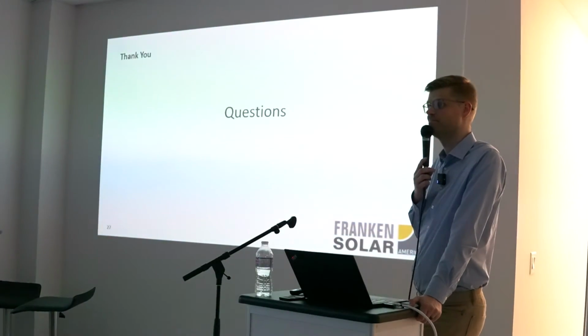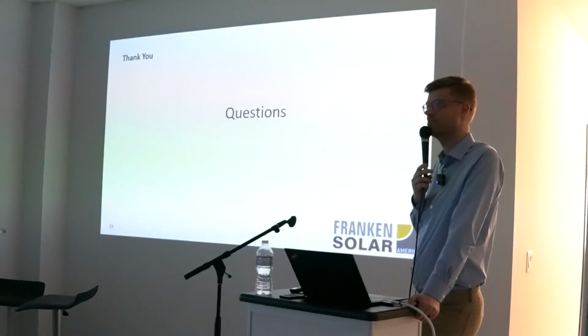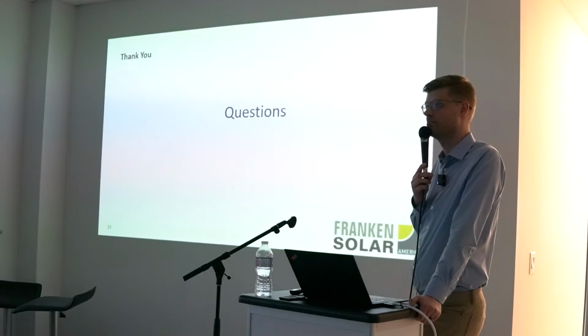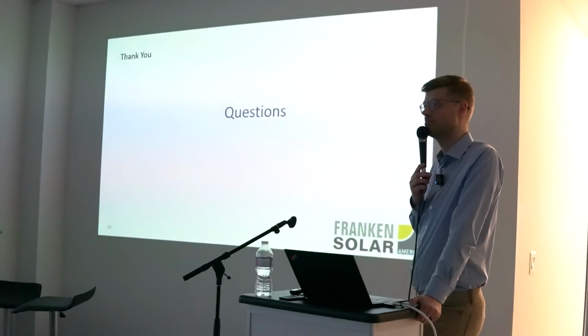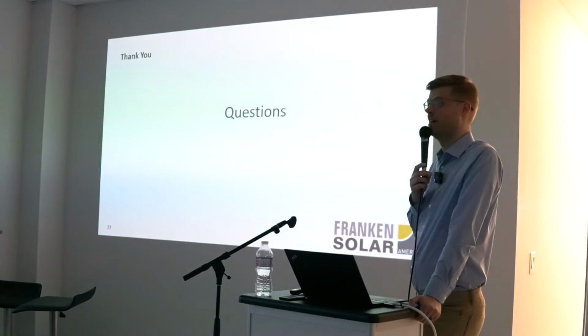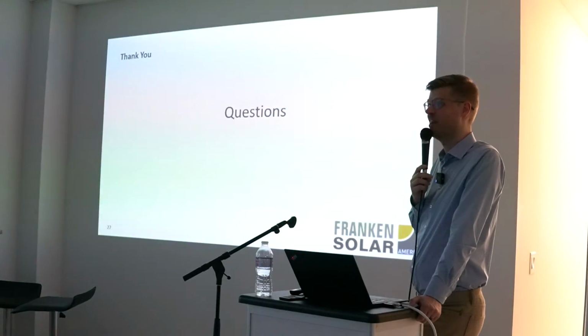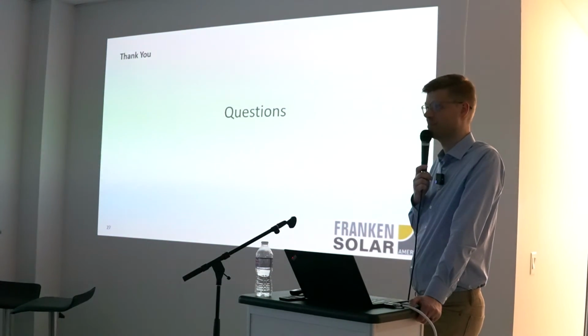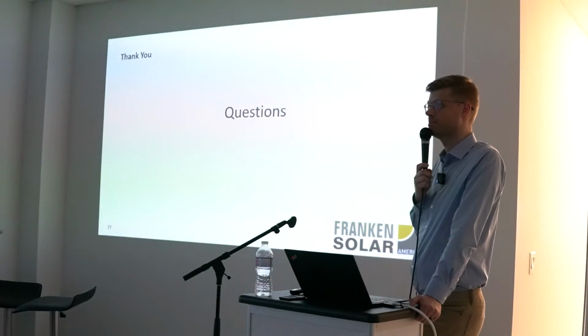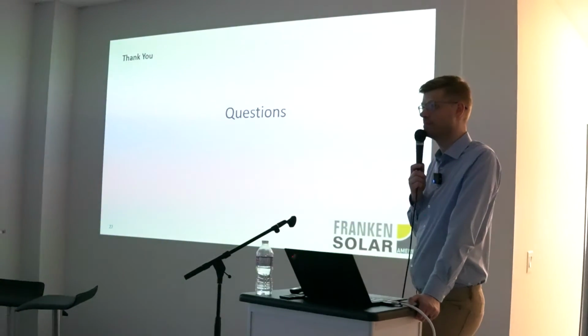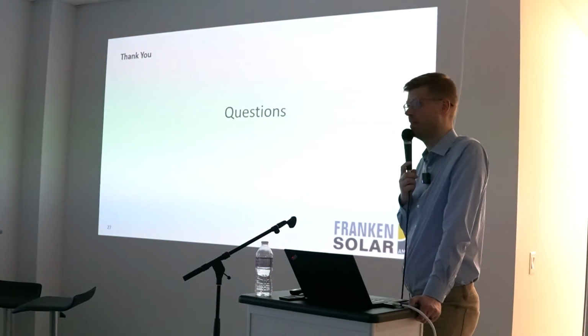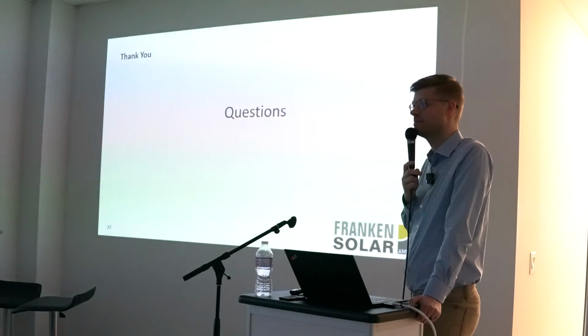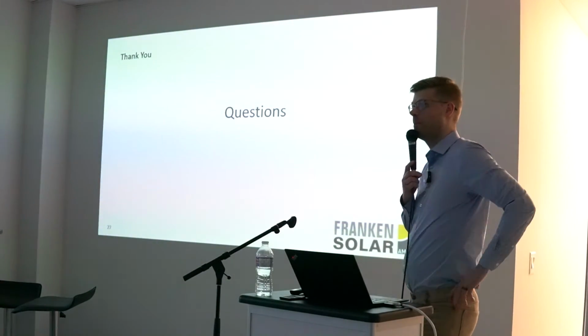Yeah. Go ahead. I have two comments. One is the SPE 1000. When SPE 1000 is conducted, it does not relieve the vendor of any liabilities that might come in the future. I'm not the expert for the certification tool. It's a statement, yeah. So that's a risk in itself. Exactly. That's a risk in itself, that if somebody's going that route, one should not forget that there is liability on the vendor that provided that equipment and had it field inspected. Exactly.